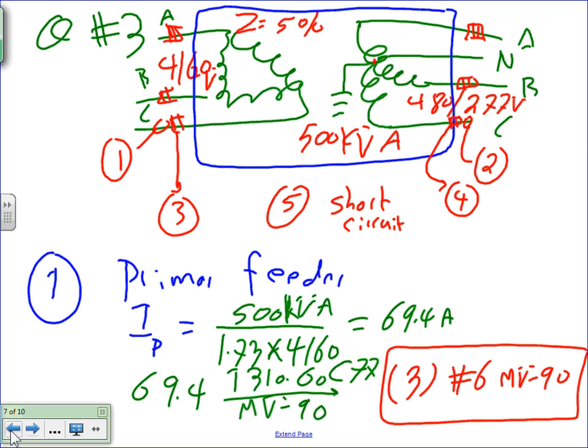Chris, do you see that big box here that I drew in blue? The blue box indicates that's a three-phase transformer. I should make it clear. Everybody knows that's a three-phase transformer. It's not three single-phase transformers, it's one big fat transformer. If it was three single-phase coils together, you're absolutely right, you multiply by three.